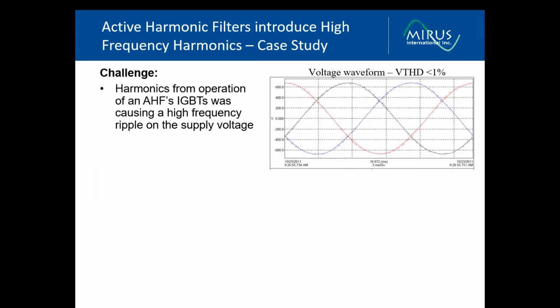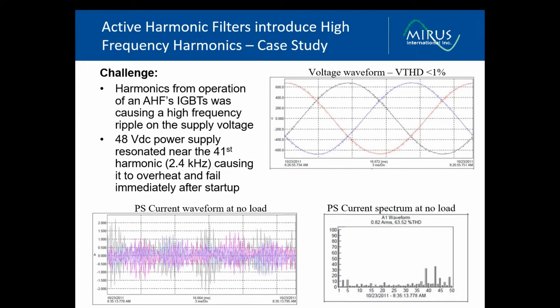I'd like to give you an example of how the high-frequency harmonics introduced by an active harmonic filter can cause problems in a power system. This was a site where I went to take some measurements. The customer was having problems with some test equipment. There was a 48-volt DC power supply on one of their testers that was failing as soon as they energized. I went and took some measurements and could see that there was very little overall voltage distortion at this site. It was less than 1%, but I could see a very high frequency ripple on the voltage waveforms.